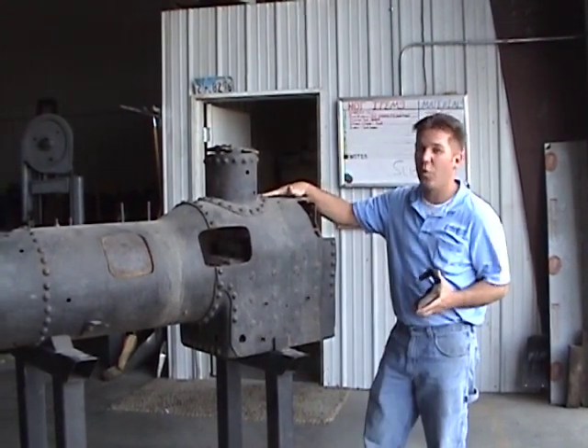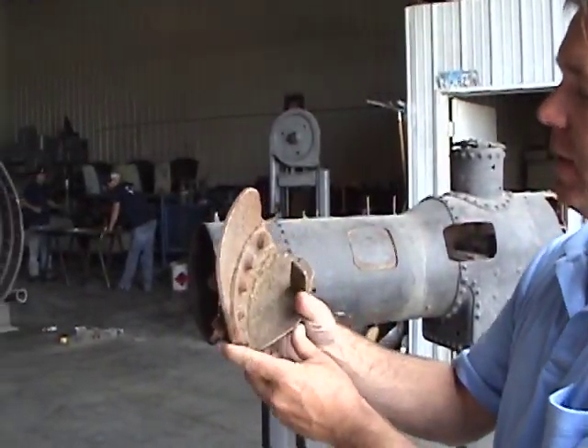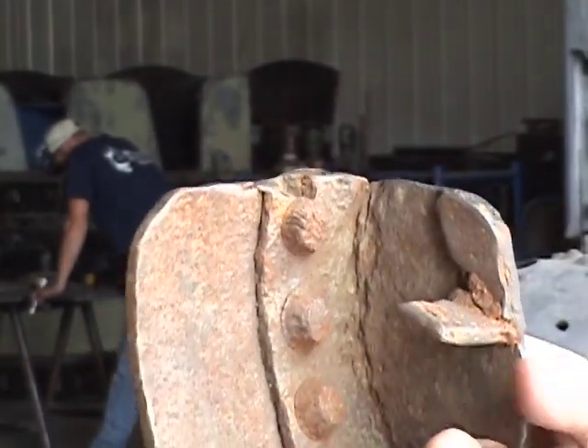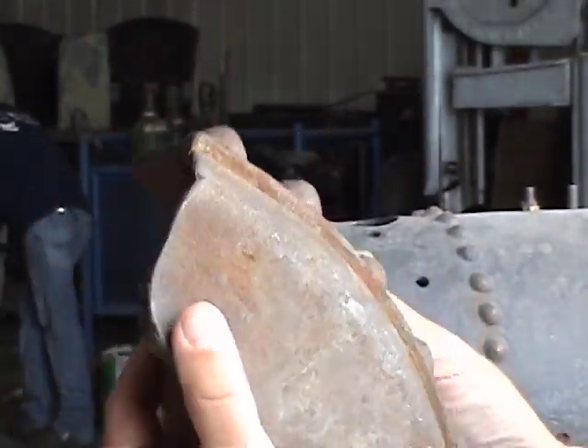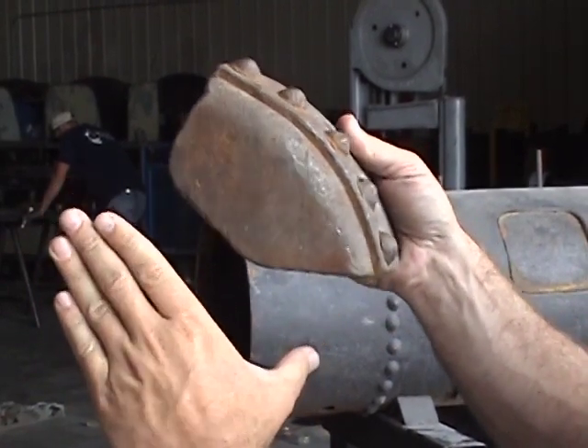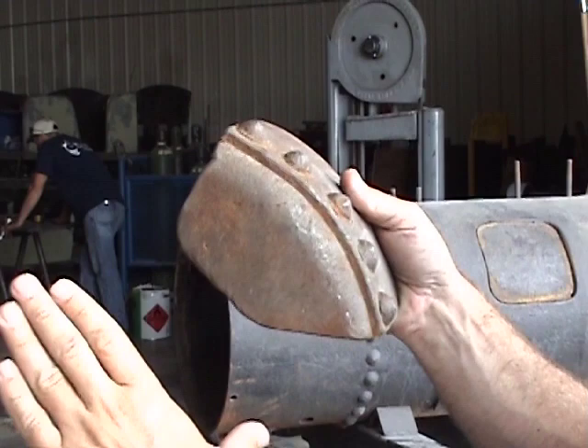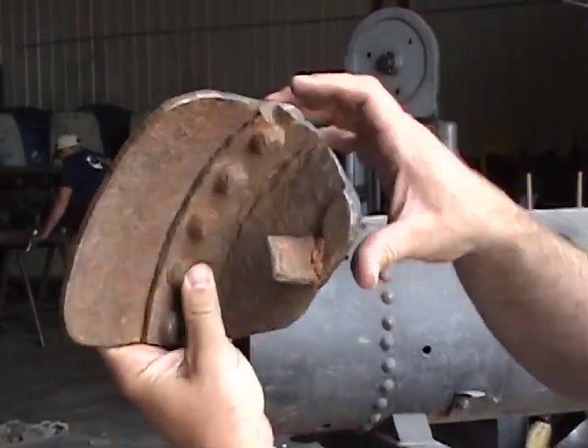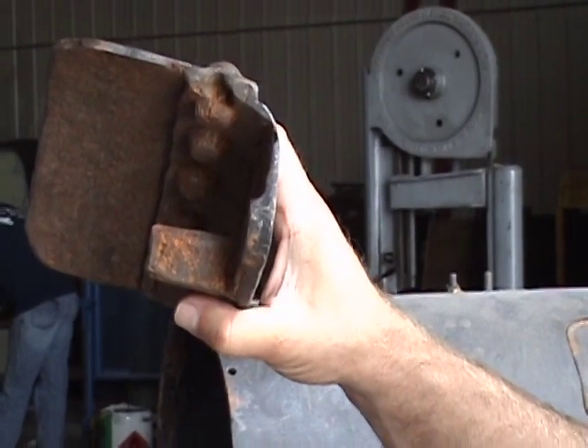This section has been taken out of this 1904 original Cagney locomotive boiler. As we bring the piece a little closer, we're going to show you what actually happens to the inside. As you can see right here, this knuckle — which from the outside is beautiful — has actually torn itself apart on the inside. The reason is greatly due to the fact that through the process of firing up and cooling down, the knuckle and door sheet expand and contract. Though the motion of my hand is quite exaggerated, this sheet is doing exactly that. The inside of the boiler that we can't see begins to tear and rip, and over the course of time this ripping and tearing thins the piece out so much that there's nothing left. So what looks good on the outside isn't necessarily always good on the inside.